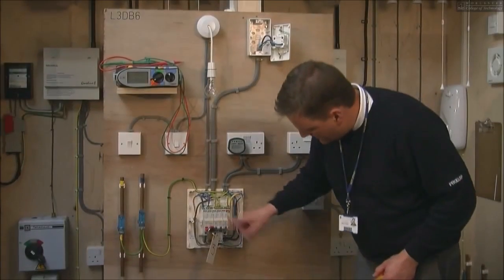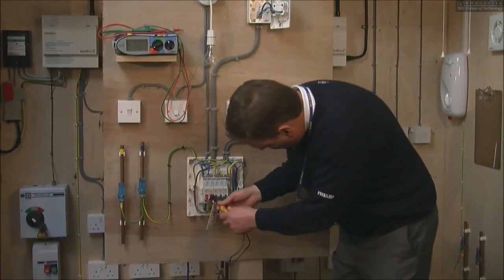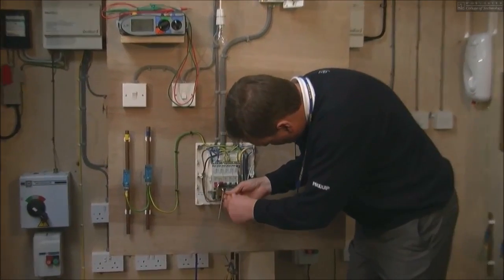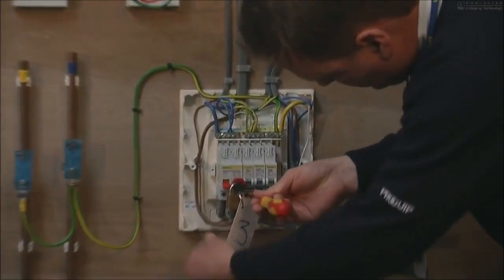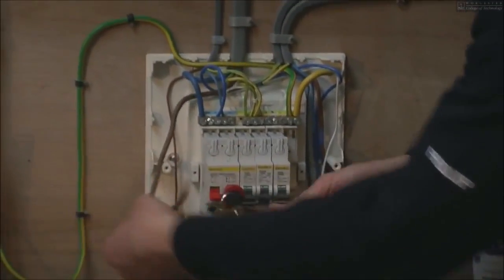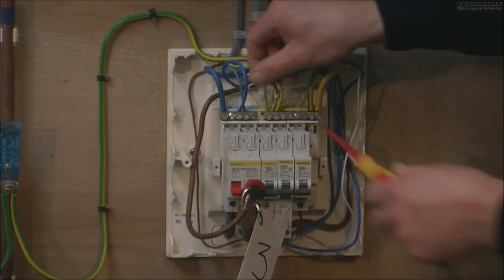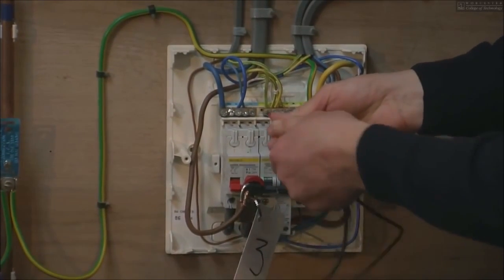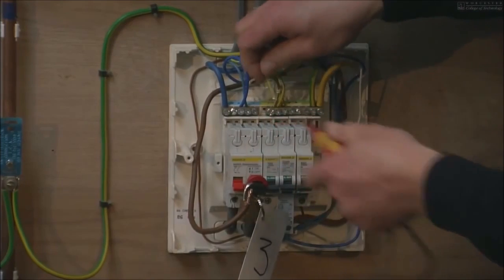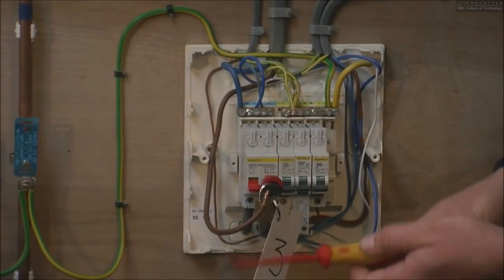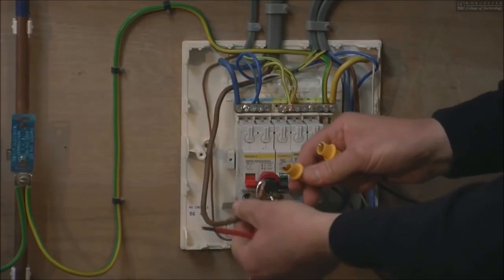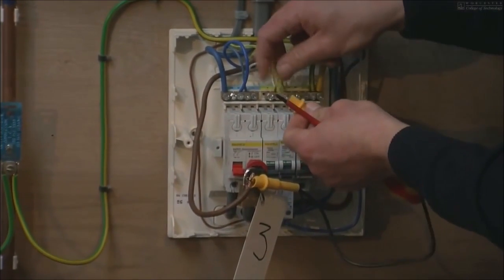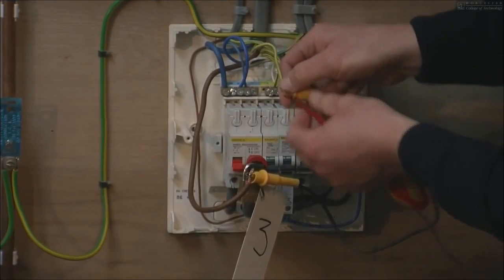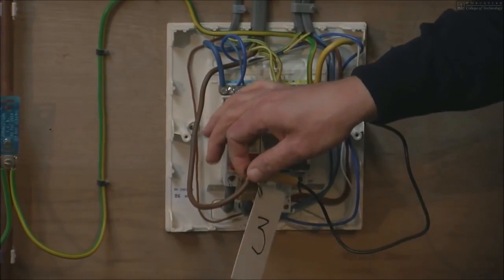We then move on to the circuits. We'll start off with the cooker supply. So I'm going to disconnect the line conductor, and I'm going to disconnect the CPC. And for this I have a little set of crocodile leads that I can just clip on to connect these together. Again, making sure that they're nice and tight.